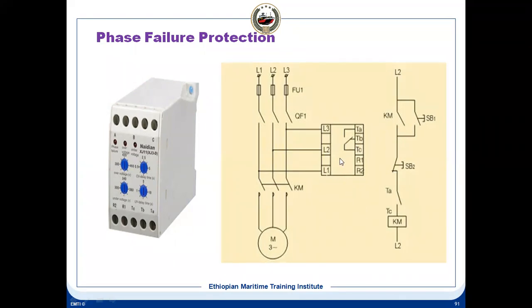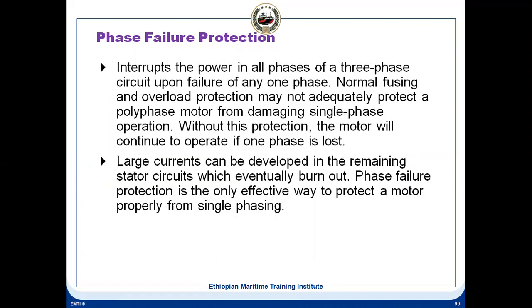So now here is how it is happening. Three-phase supply L1 and L2 is given here, and when any of the phases fails, this relay will open here and trip the main contactor. So this is called phase failure protection. This will interrupt the power in all the phases of a three-phase circuit upon failure of any one phase. So if any one phase fails, it will interrupt the power.